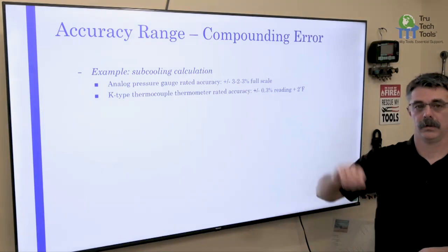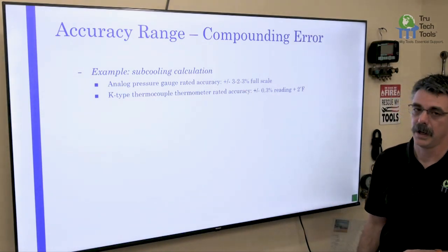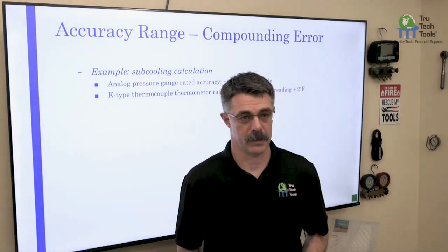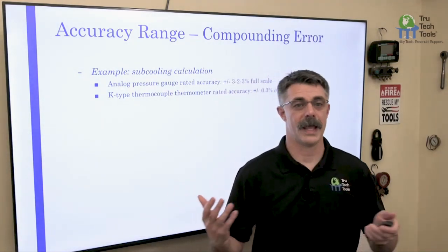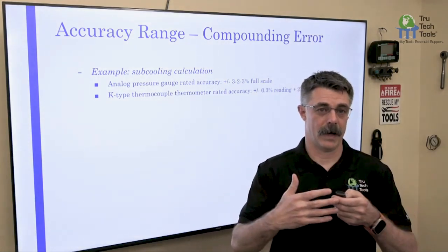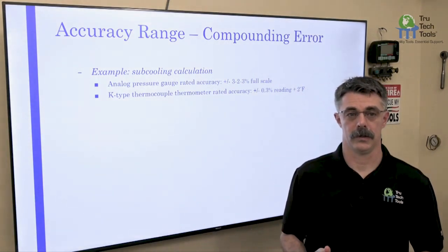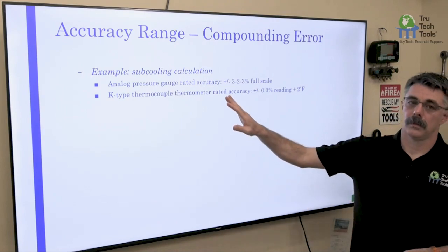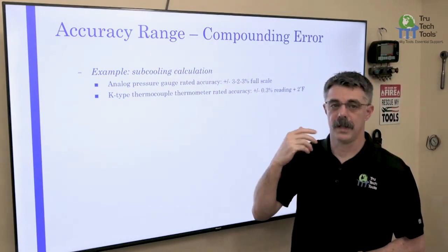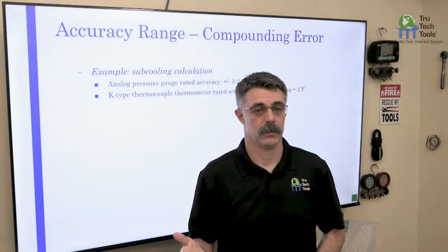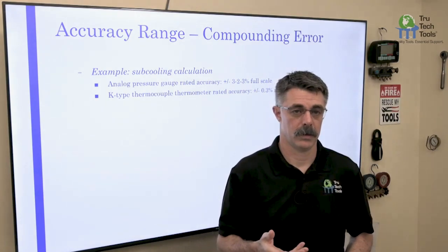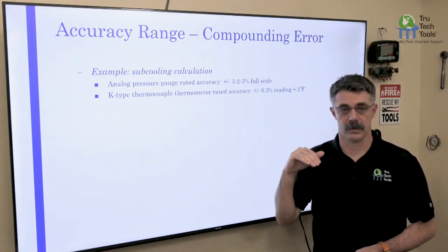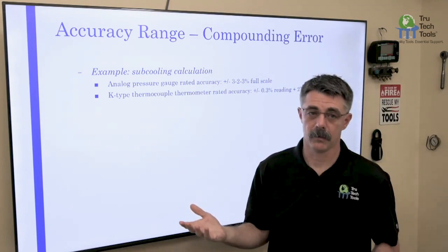Let's talk about subcooling calculation — something near and dear to all of us in this industry. Subcooling is a calculated value, not a measured value. We take two different readings and feed them into one to make a calculation. With subcooling, this becomes challenging because we have two different instruments and a compounding inaccuracy — errors that stack on top of each other and depending on how they work, can really throw things off.